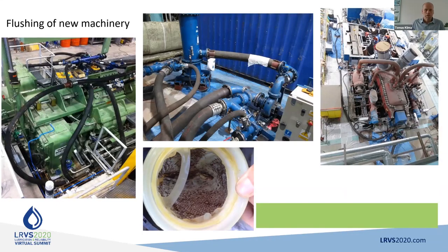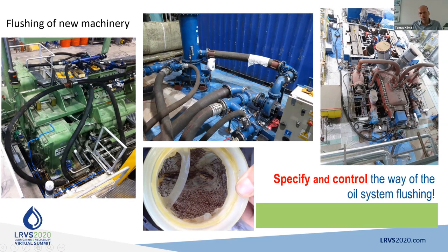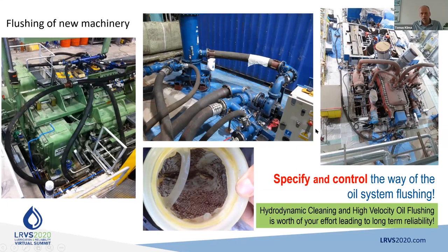A few pictures of how new machinery could be assembled: a large flushing skid, a lot of hoses on, for example, here left on the steel mill, or a retrofitted turbine. And we pay attention to the process and recommend to the customer that they should specify and control the way of the flushing, not just let it be written on paper. Hydrodynamic cleaning and high velocity oil flushing is worth your effort, leading to long-term reliability.